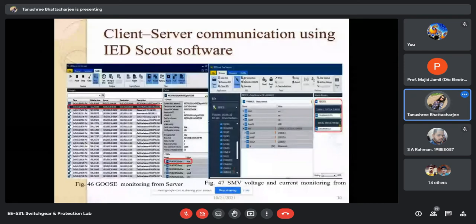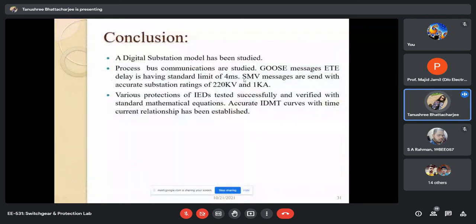So, the conclusion of the complete study: a digital substation model has been studied here. Process bus communication, GOOSE and sample measured values have been studied. Three types of protection have also been tested. With this system, distance protection and more types of fault can also be measured, but as we do not have a licensed Omicron, that is why we have studied these three types of protection.